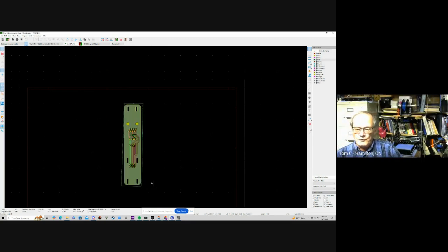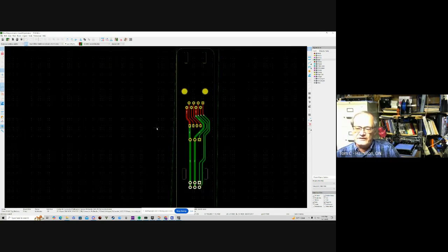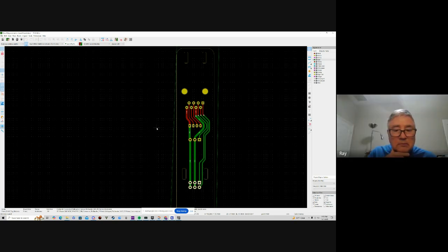Thanks, Chuck. Just an observation, but I'm just curious. Have you had a look at the current drain on that 6-volt power line and ground for 3 servos? You might be overloading what you can comfortably put through an RJ45 connector pin, or a trace at a certain width. Well, I'd worry about the connectors. RJ45s are a pretty light duty connector. I want to say they can handle an amp or something like that. And that's what I just looked up, Doug.